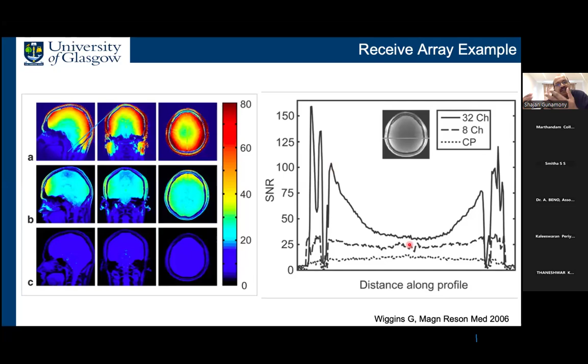Here you can see the image from each of these 32 individual elements. And now you can see the SNR that you get from this coil. In the bottom row, you see the SNR of a birdcage coil. It will be quite low, but it is quite flat, right? Because it always produces a very homogeneous field. In the middle row, you see the SNR profile of an 8-channel coil. And on the top, you see the SNR profile of a 32-channel coil. You get so much more signal with this one in the periphery and also in the center. That's really the advantage of high channel count coils.